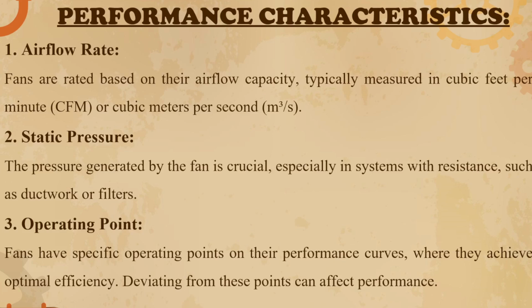Performance characteristics of a fan. First is the airflow rate. Fans are rated based on their airflow capacity, typically measured in cubic feet per minute or cubic meters per second. Second performance characteristic is the static pressure, which is generated by the fan. It is very crucial, especially in systems with resistance, such as ductwork or filters.